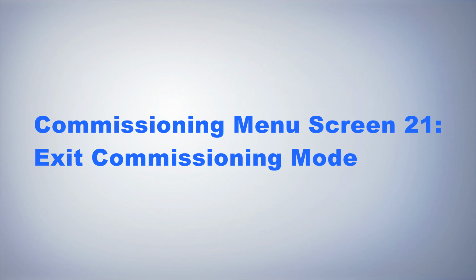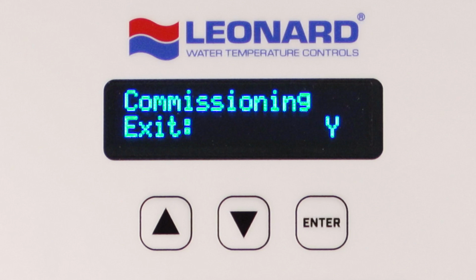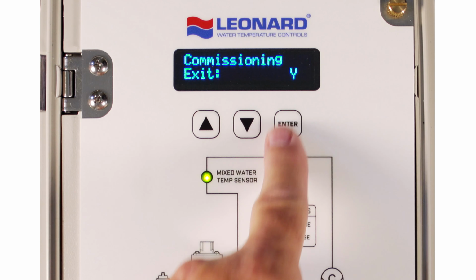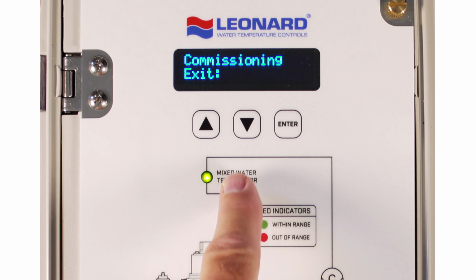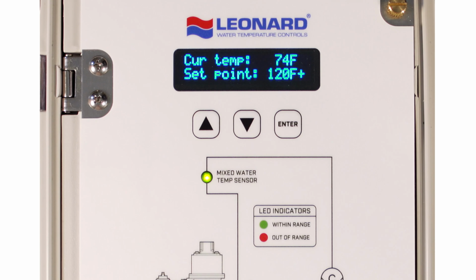Commissioning menu screen 21. Exit commissioning mode. Pressing down 20 times displays Commissioning Exit, No or Yes. This feature will allow users to exit the commissioning menu or continue. Selecting Y will exit commissioning mode without saving any changes made to the commissioning values. Selecting N will keep the control box in the commissioning menu.